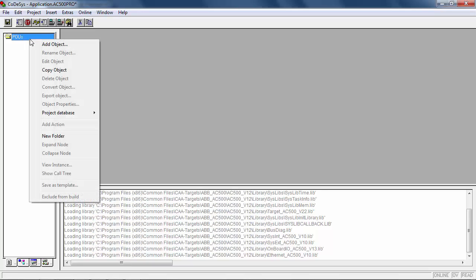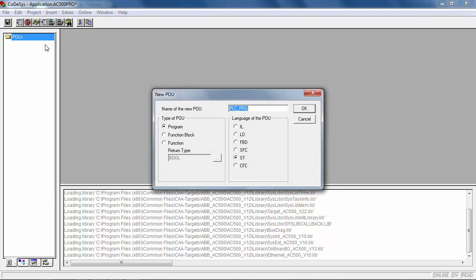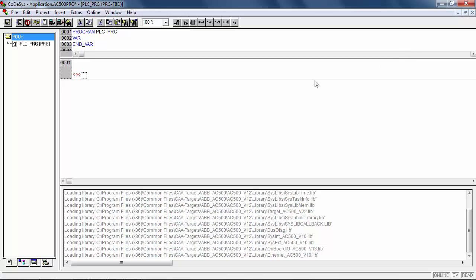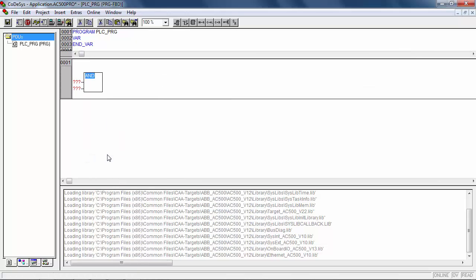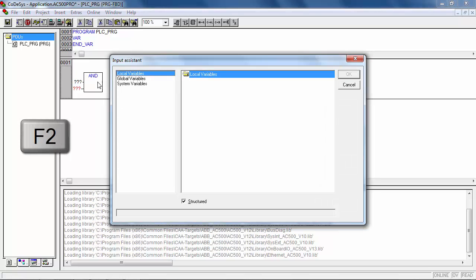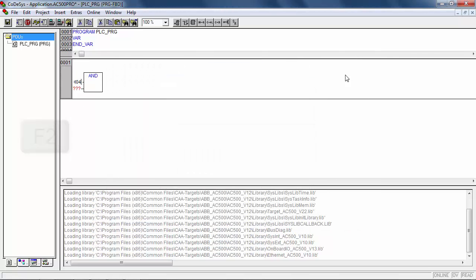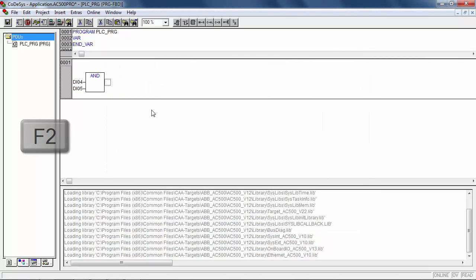Add a new POU with the help of add object function, accessed just by right-clicking on the POUs folder. Once a POU is created, we could start writing a simple program for demonstration using the function block diagram. Next action will be to add the necessary logics and attach to the inputs and outputs of AC500 eCo CPU previously defined.